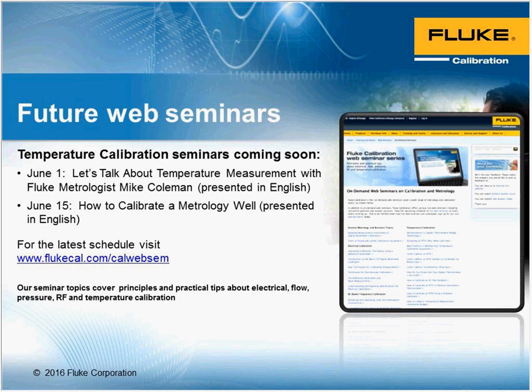Okay, question from PM2. What is the temperature difference between the reference sensor and the unit under test in a typical dry well to maintain for the uncertainty budget? My best way to answer that: it all comes down to the types of units that you're using. There are different grades of dry wells, ranging from industrial types that will have much wider uncertainties, as wide as ±1, to tighter ones that get all the way into the point-ones or less. So it's just the range or the type of dry well.